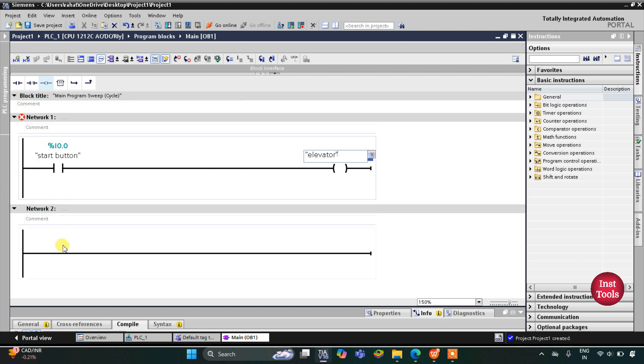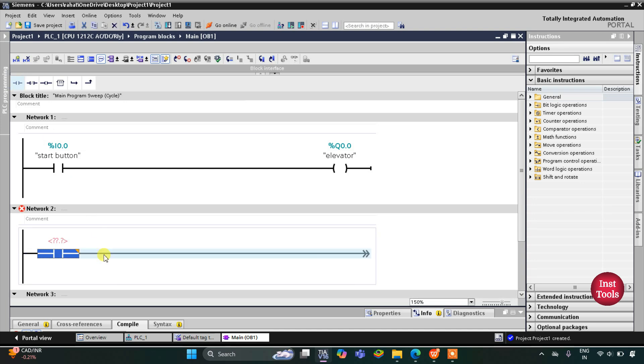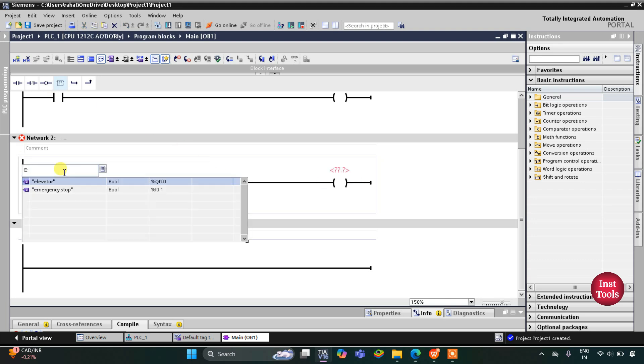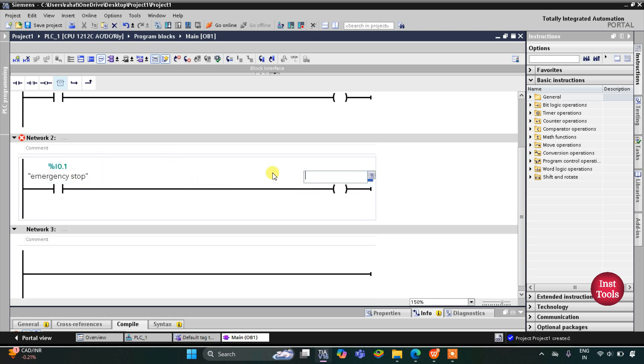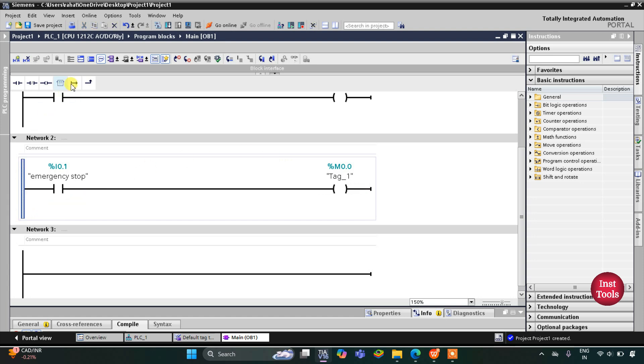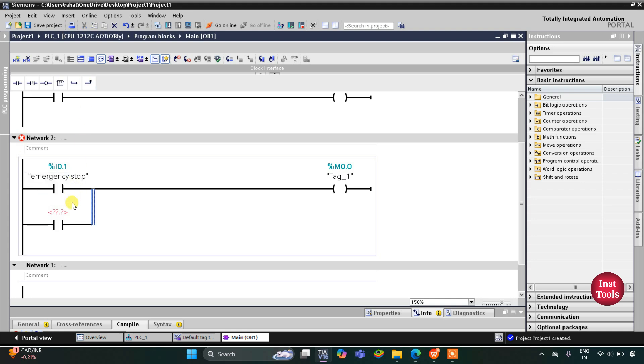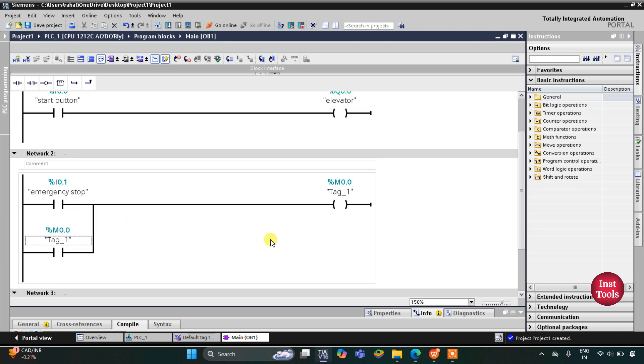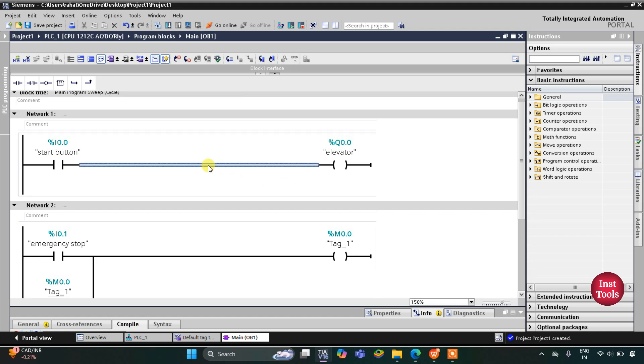In the second rung, this normally open contact is for the emergency stop, and then a coil that will be used for a memory bit. When the emergency stop button is pressed, memory bit M0.0 gets activated. I will latch it here by opening a branch, adding a normally open contact for M0.0, and then closing the branch.